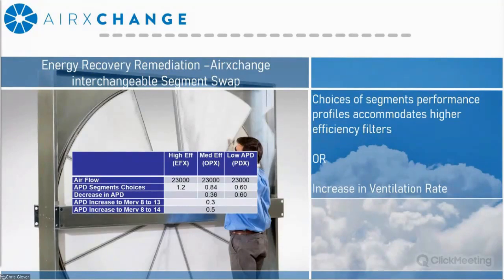But it's really important to keep in mind, as you're making these system changes, there's going to be a little bit of loss of performance. In most cases, that loss of performance is compensated by the system not having to work as hard, because during the pandemic, we don't have as high occupancy as we once did. But I just like to demonstrate that there are options available for existing systems in the pandemic environment if you're looking to achieve either higher ventilation airflow delivery to the space, or higher filtration, or a combination of both.